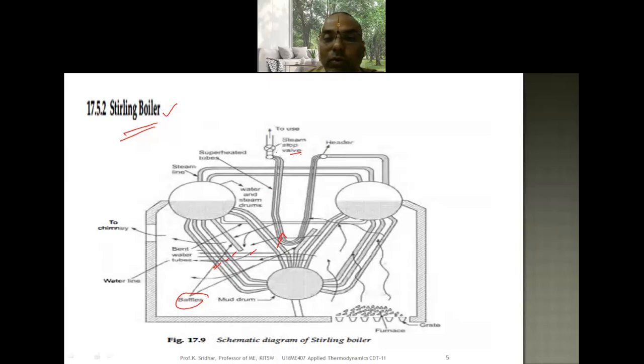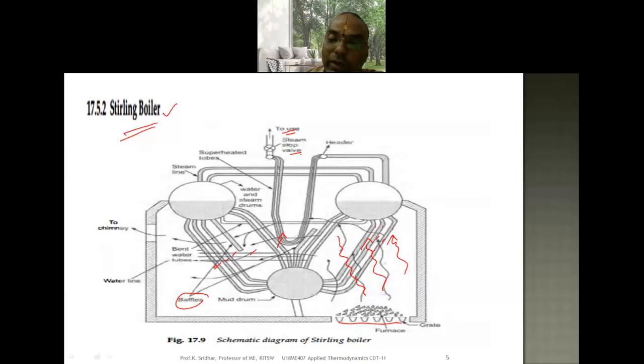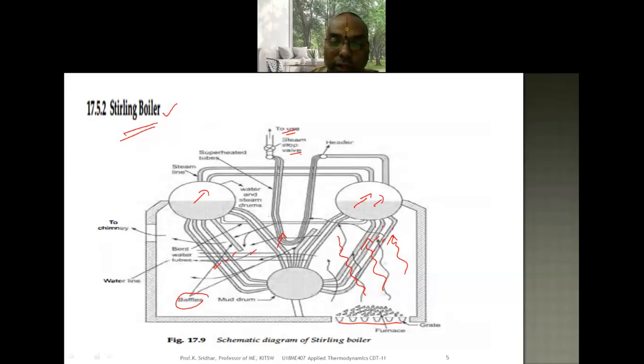The superheated steam is taken from the steam stop valve as required for the application. There is also a header. The grate is the surface over which coal burns, and flue gases flow and strike the bent water tubes, converting the water inside into steam. This steam travels along the steam line to the superheater tubes. A mud drum is provided at the bottom to collect unwanted particles, which are then removed from the boiler.